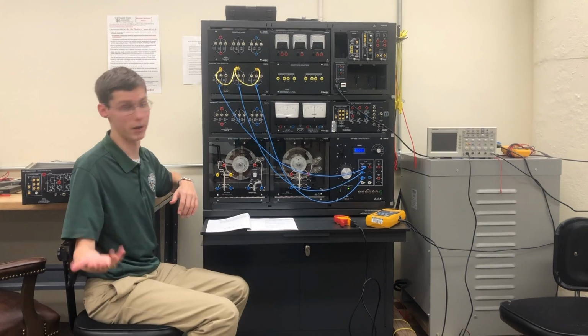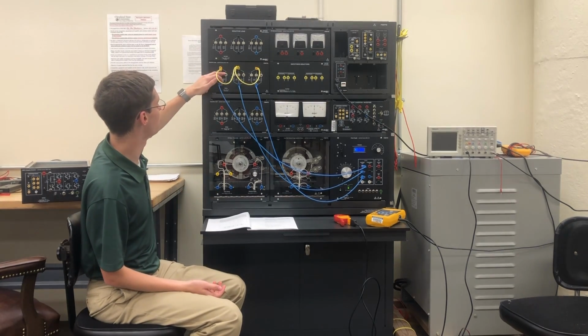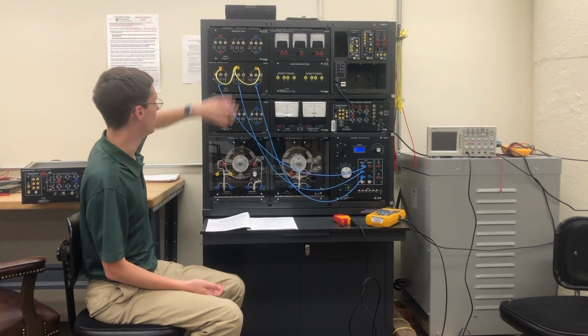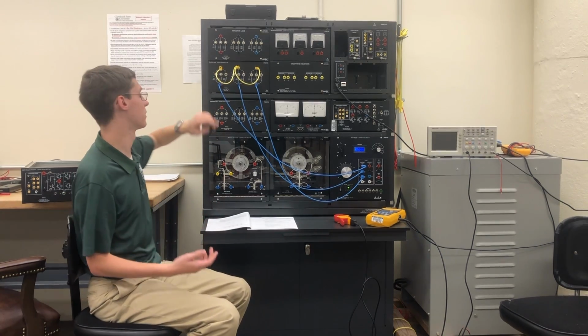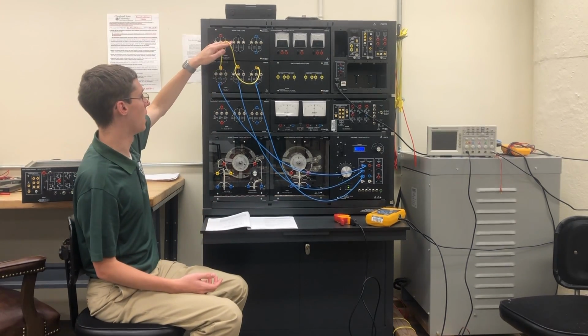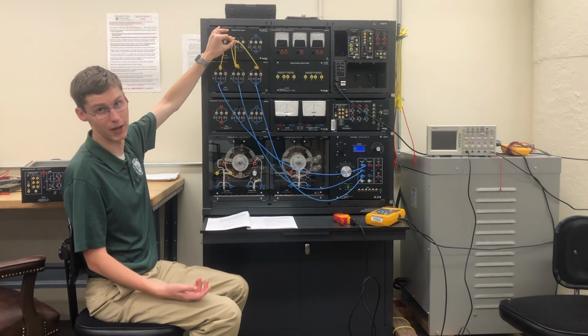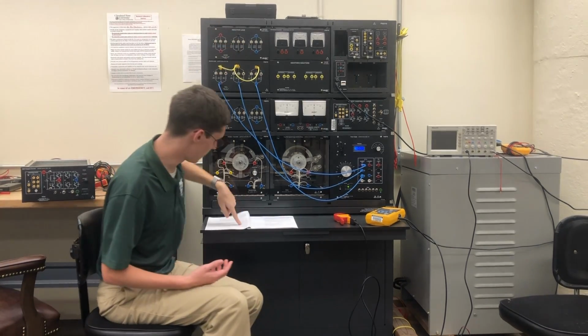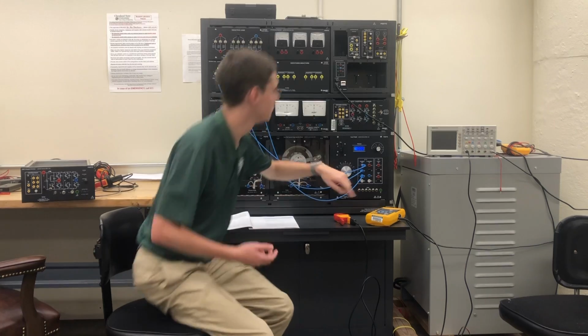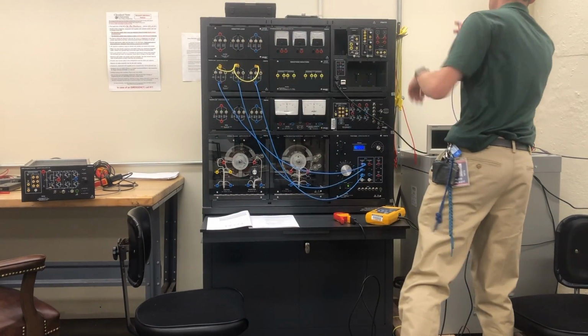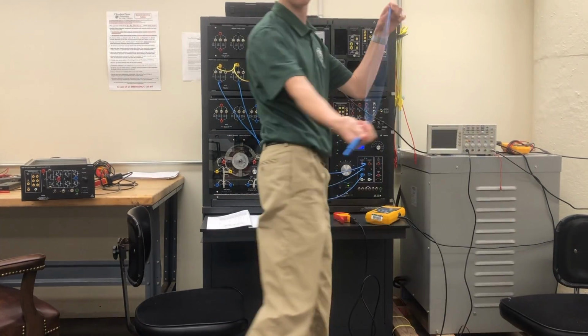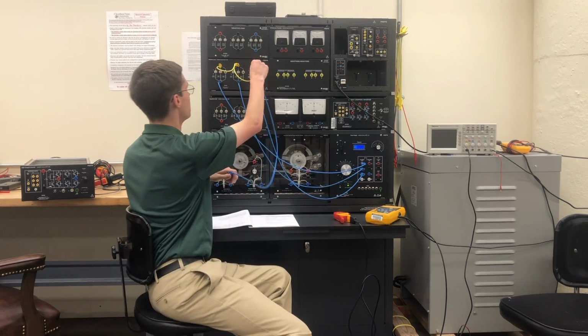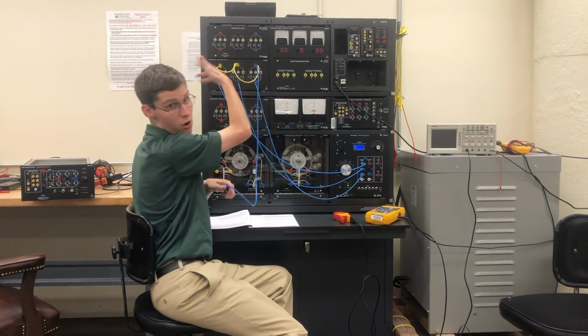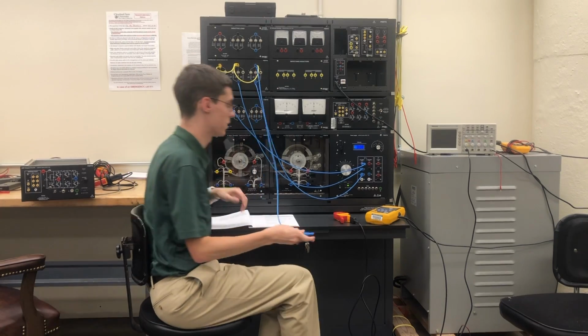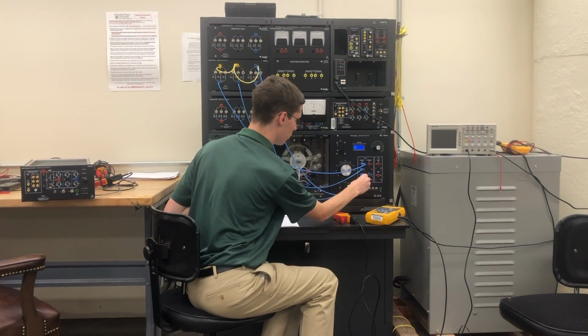Obviously, this circuit is 300 ohms, so all you're going to do is flip the switch up 300 ohms for each of them. And since it's a Y-connected circuit, all of these resistors will be terminated into a common connection here. It wants a neutral return, so I'm going to add that. I'm going to grab a blue cable from the side of the bench, one blue cable, and hook it up to any one of these because they're all shorted together. It's just a wire, just like a node, and you'll run it down to the neutral down here.